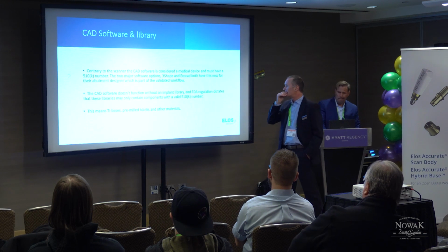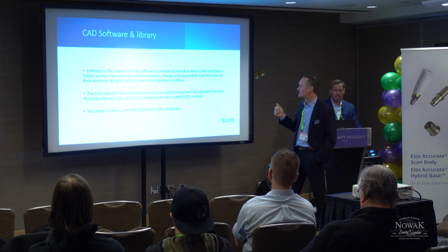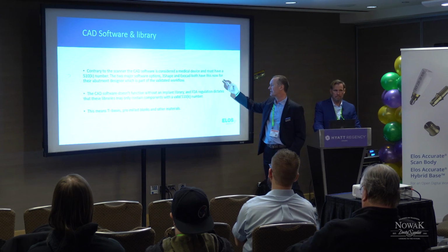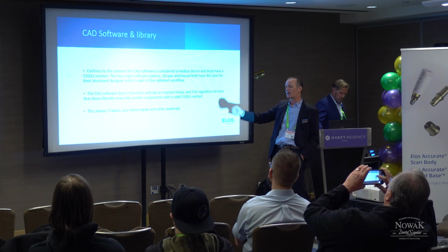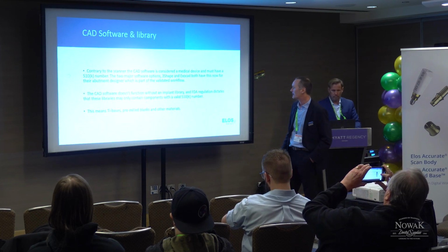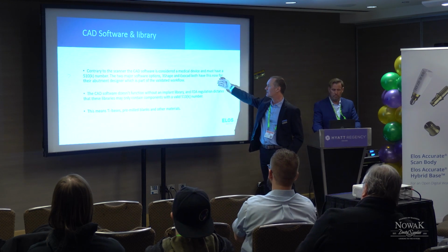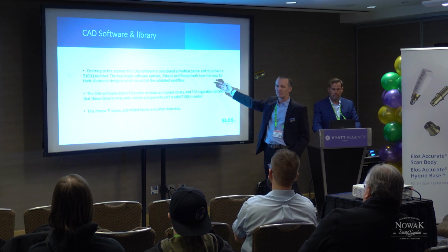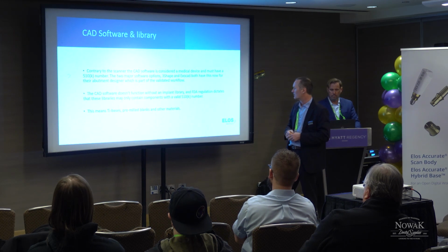So, as I mentioned before, the scanner is not a medical device, but the CAD software is, and I don't know, maybe sometime in the future the scanner will also have to have its own 510K number and be verified as a medical device, but nowadays it only goes for the CAD software. So 3Shape and Exocad have gone through the rigorous exercises of demonstrating that the software is okay, cannot be tampered with, and delivers the right output when you work with it.